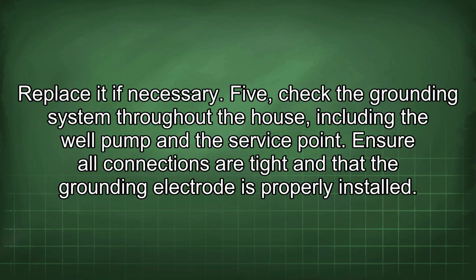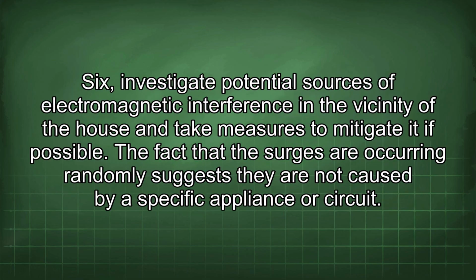5. Check the grounding system throughout the house, including the well pump and the service point. Ensure all connections are tight and that the grounding electrode is properly installed. 6. Investigate potential sources of electromagnetic interference in the vicinity of the house and take measures to mitigate it if possible.